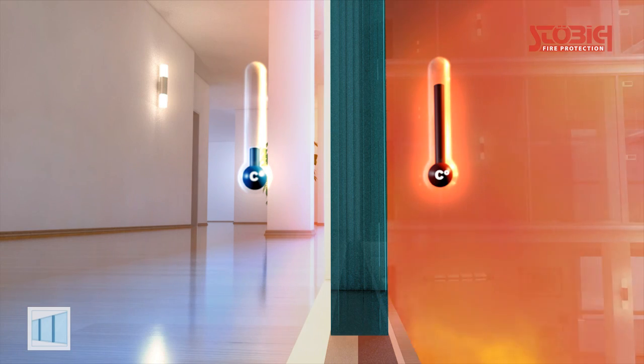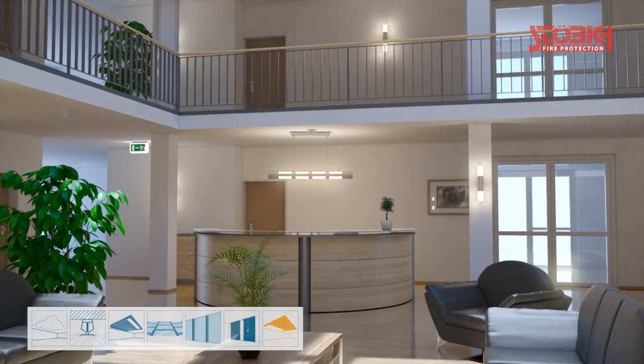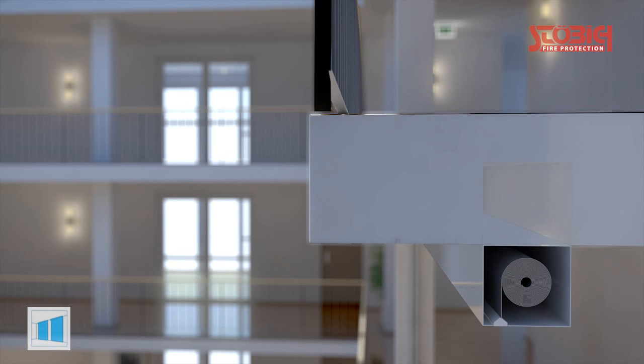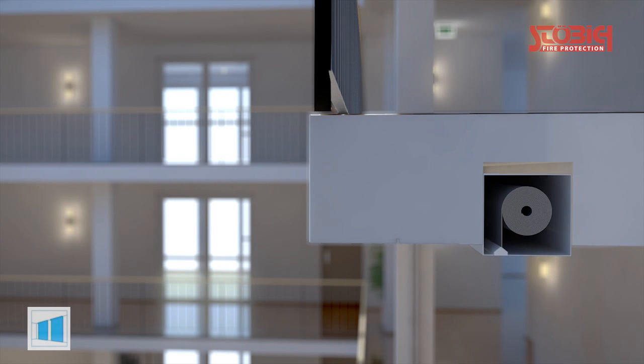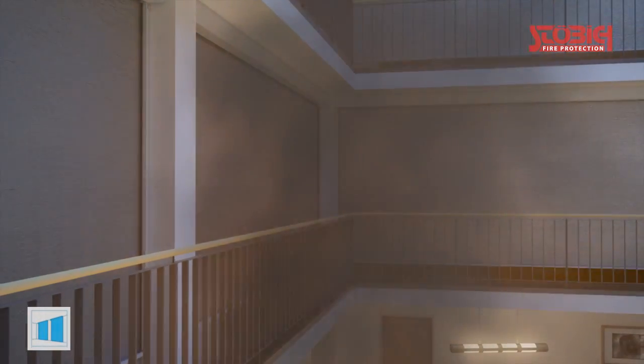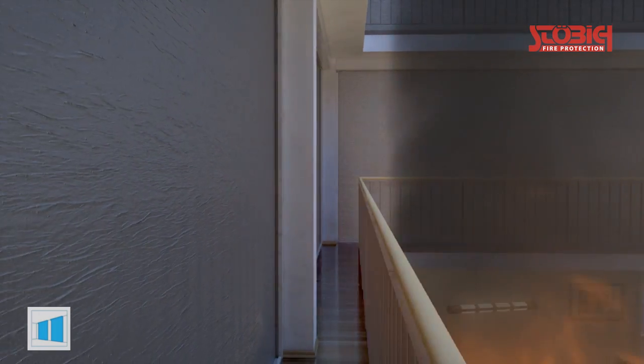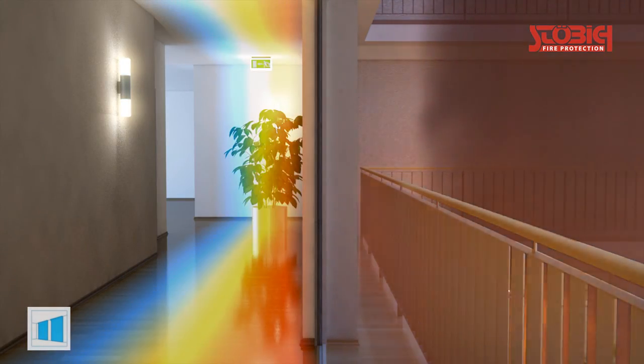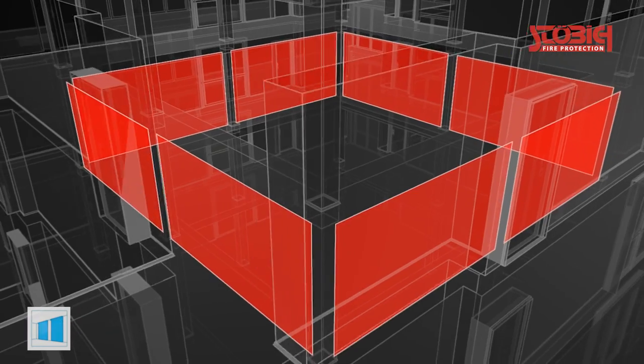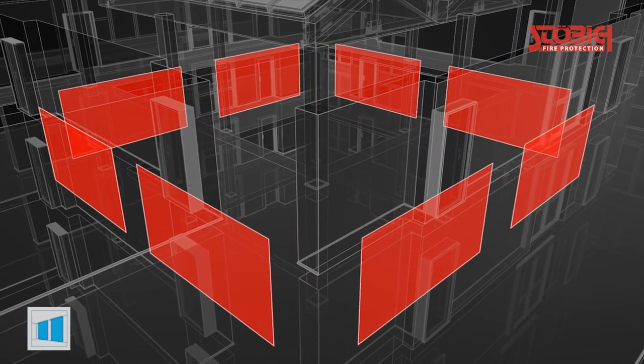The installation of a textile fire protection closure is an alternative to the lateral compartment with fire protection glass. Due to their low weight and the small casing dimensions, these systems can be mounted nearly invisibly under the ceiling or in false ceilings. But the textile closures must also resist elevated temperature effects, and it can lead to restrictions in the escape route area, despite the use of special fabric with high radiation resistance. An advantage over a fixed glazing is that the fabric surfaces are rolled up in the casing in the standby position. In case of an alarm, the closures seal the opening, and so they offer, in their standby position, an unrestricted use of the room concept. The closing of the ceiling opening is more efficient with a textile system.